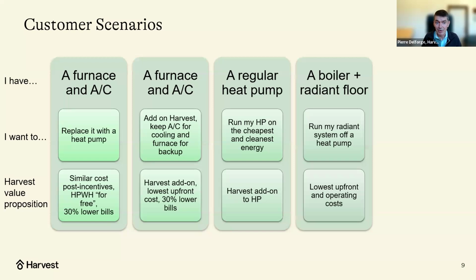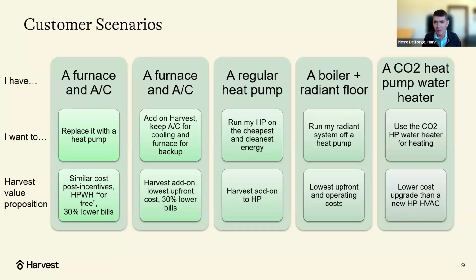Another scenario is radiant floors and gas boilers. So as I mentioned earlier on, the Harvest system can feed radiant floors and basically retrofit those to a heat pump, with all the benefits of, again, load shifting and high efficiency. And the last one is, if some of you are already adopters of the Sanco2, we have a lot of fans and aficionados of the Sanco2 heat pump, which is a really good heat pump, CO2 refrigerant. Then you can keep it and make it go further by adding hydronic heating to it with a Harvest pod.